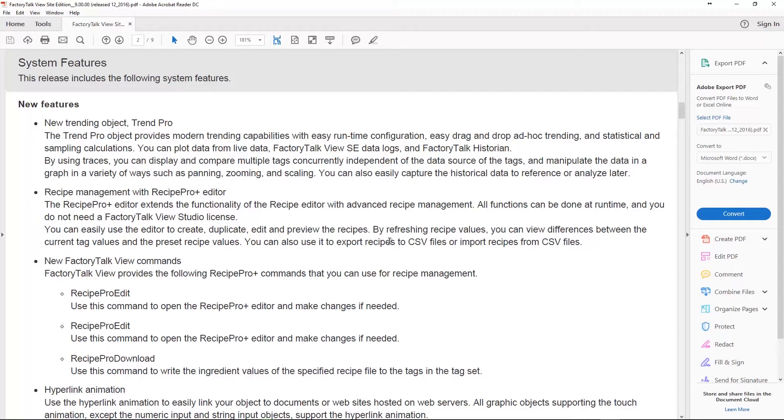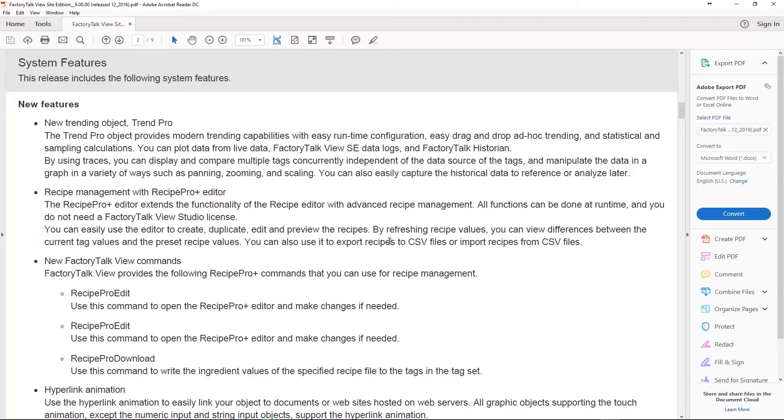They're talking about the Recipe Pro Plus Editor specifically here and saying it gives you advanced recipe management. All the functions can be done at runtime so you can create new recipes, delete recipes, all that and you don't need a FactoryTalk View Studio license to do that. With that said, you can also use it to export recipes to CSV files or import recipes from CSV files. I know back in the day in the RS View 32 days I actually wrote a VB app that would input the InTouch Wonderware InTouch CSV recipe files into Recipe Plus, so having this feature built in is so cool.